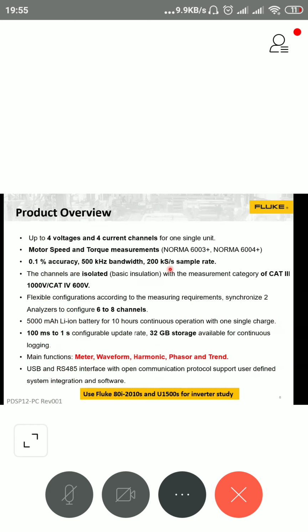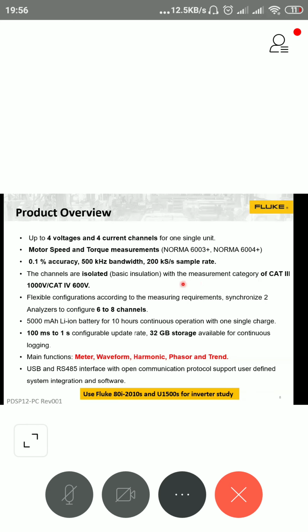Now, the interesting part of this equipment is that the channels are isolated, and it carries the highest safety rating, category 3 and category 4. Most precision power analyzers are designed for lab purposes, so they generally carry category 2 or category 3 safety ratings. But this is the first equipment which carries category 3 and category 4 safety ratings. The importance of that is when you're doing a measurement in an electrical panel.